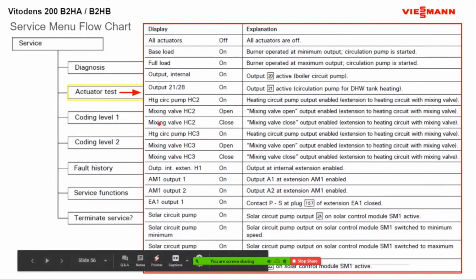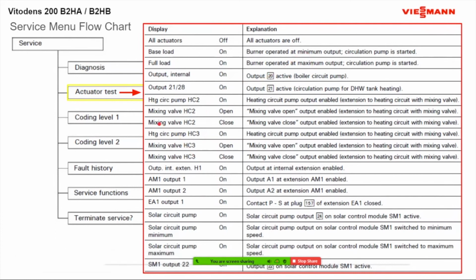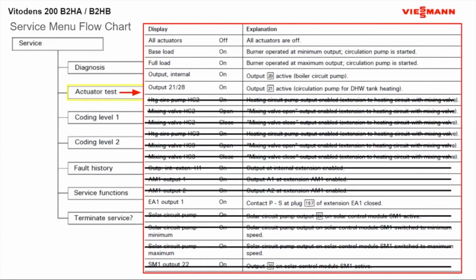If you do have our mixing valves tied to the boiler, you can go here, open and close them, put them in the center position to make sure that you wired them correctly, because these are powered open, powered closed mixing valves. So if you got them wired wrong and you come to your actuator test and you see it's closing instead of opening, all you have to do is reverse your wires, and you're good to go. If you don't have any of the stuff plugged into the boiler, you're not going to see any of that stuff for your actuator test. So basically you might see 3 or 4 things. If you have your 2820, you might see that as well. But if you don't have any of that stuff plugged into your boiler, you won't be able to see any testing for it.